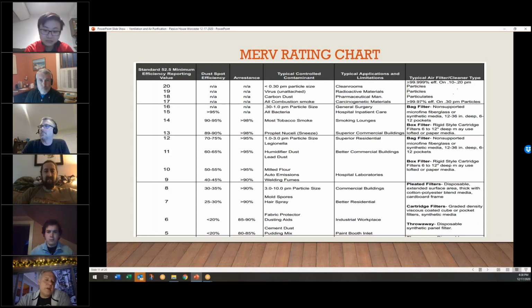The thing with putting MERV 13 filters into existing systems is you just have to be careful about the effect on the system. Initially, out of the gate, a MERV 8 filter and a MERV 13 filter have pretty similar pressure drops, but the MERV 13 filter will get dirty much faster. So if it doesn't have a MERV 8 in front of it, and you're just taking a MERV 8 out and putting a MERV 13 in, that's going to fill up pretty fast.